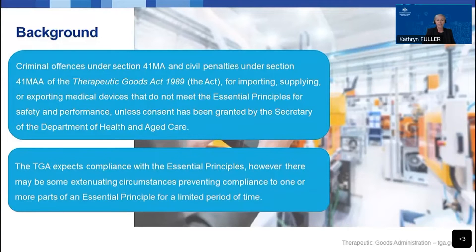Let's begin with a refresher on why you may need to apply for consent for non-compliant devices. The reason you may need to apply for consent to import, supply or export medical devices that are non-compliant with the essential principles is because there are criminal offences under section 41MA and civil penalties under section 41MAA of the Therapeutic Goods Act if you supply non-compliant medical devices unless consent has been granted by the Secretary of the Department of Health and Aged Care. If there are extenuating circumstances preventing compliance for a limited period, you can apply for consent even though there are some non-compliances.